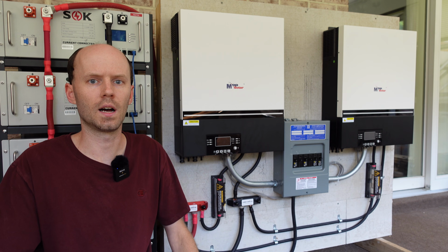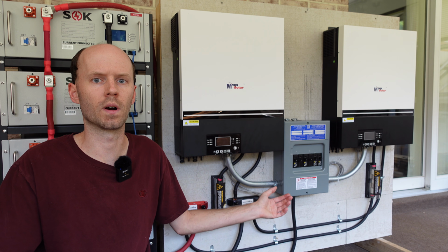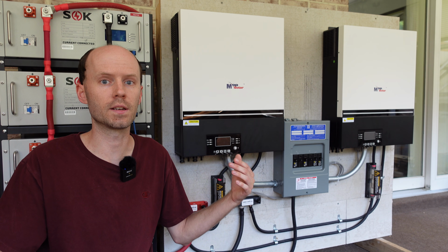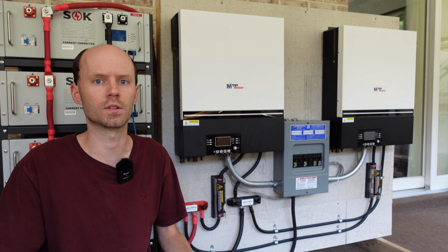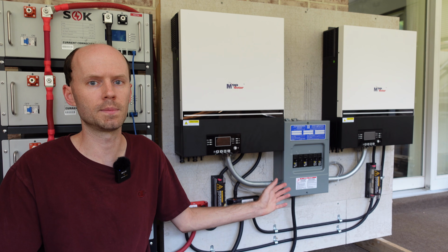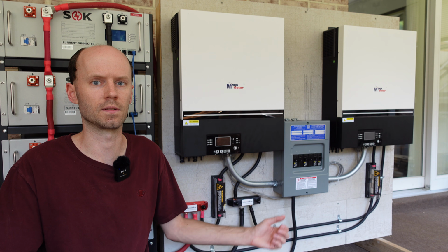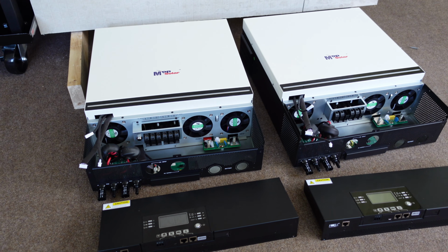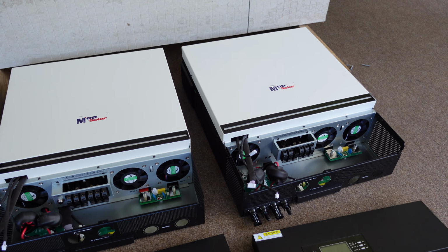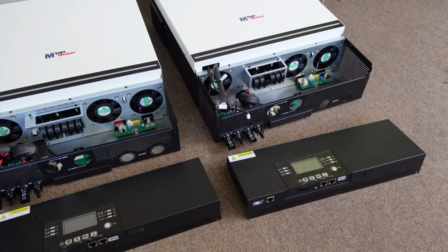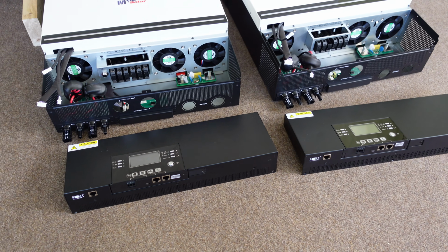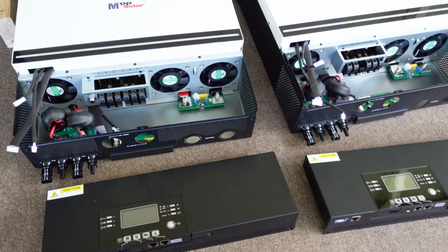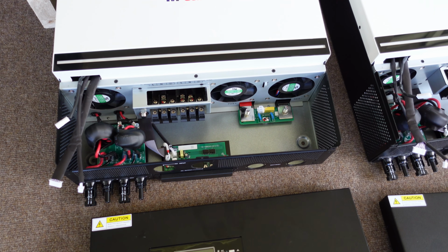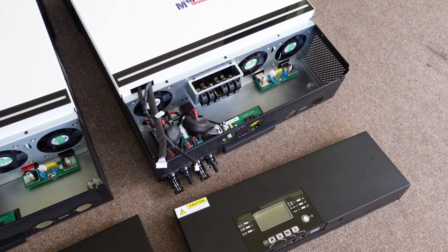And when we do start getting into the AC wiring, I like to always make a note that if you have any questions or don't know what you're doing, you should not be attempting this and you should contact an electrician. All right, so I've got my two LV6548 inverters here from MPP Solar. I've got both of the front panels removed from each inverter. This is needed to access both the terminals for the battery, AC, and for the mounting holes on each inverter.